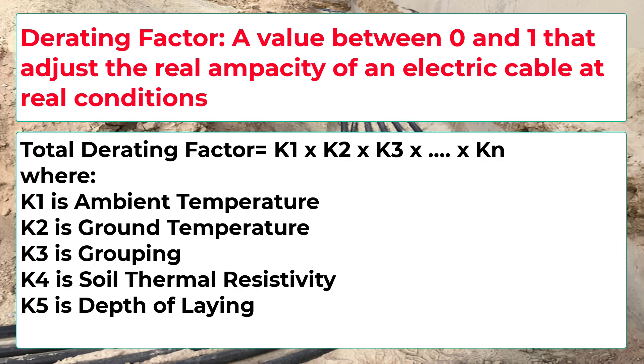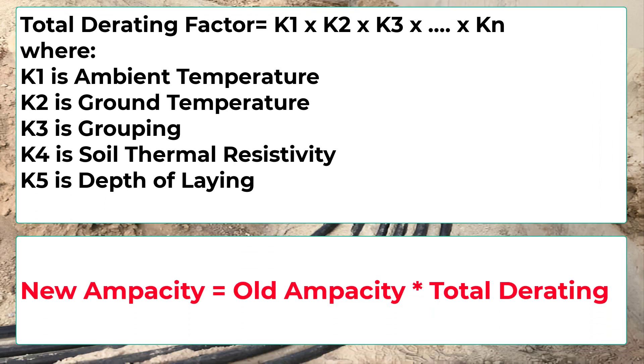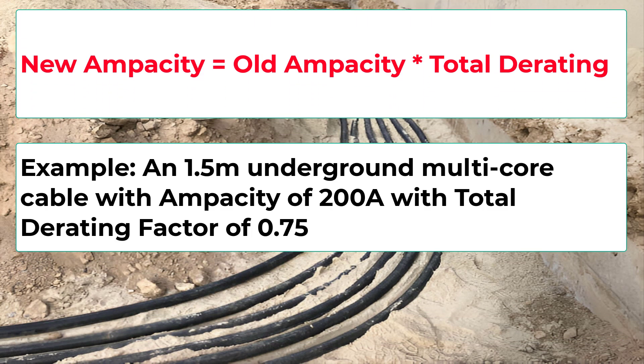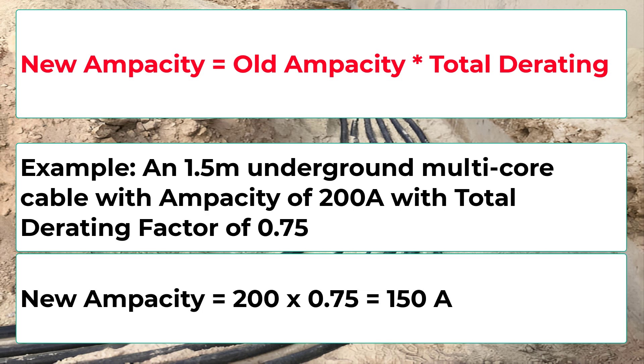You then calculate the new ampacity of your cable by multiplying the default ampacity value by the rating factor. For example, if you have a multi-core cable with a default ampacity of 200 amperes, installed underground at 1.5 meters depth, with an ambient temperature of 45°C, and alongside other cables — using tables, all these factors together give a derating factor of 0.75. So the new safe ampacity equals 200 A × 0.75 = 150 amperes.